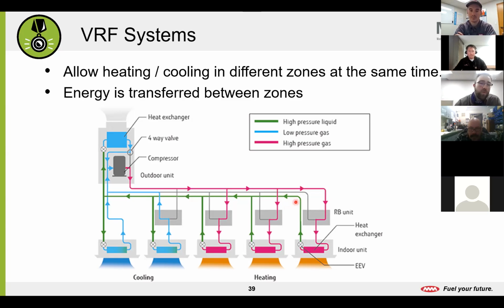Now, normally, on a traditional system, we would just send this liquid back out. Absolutely, we can make these available for you guys. We can send this liquid back out to our condenser. And what that condenser does is it takes that liquid and utilizes it to start making more hot gas.